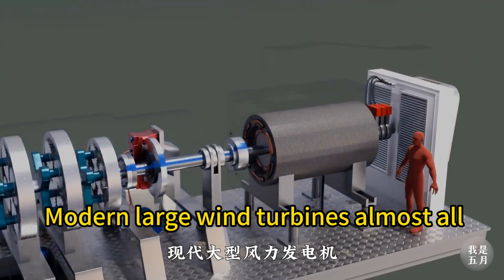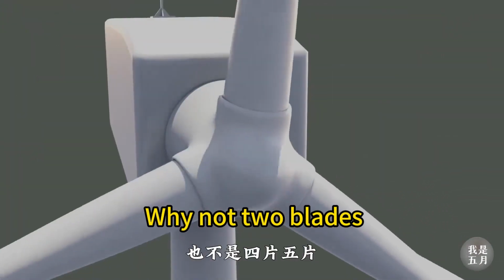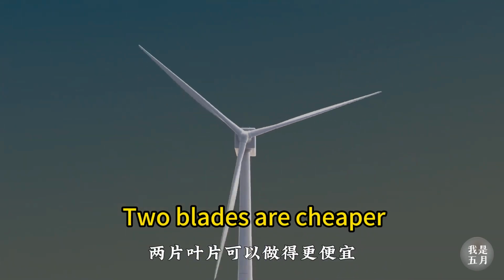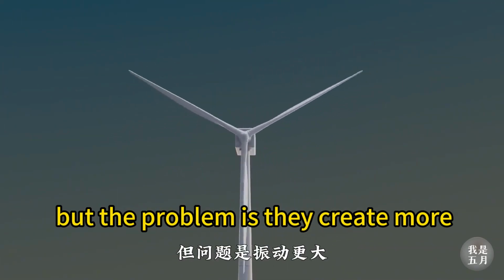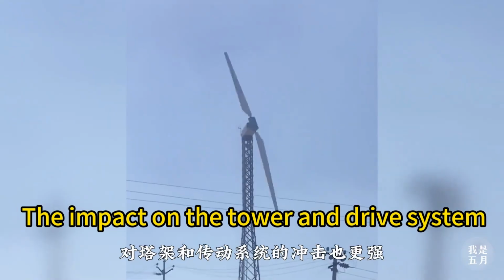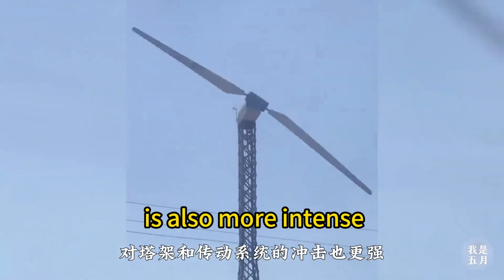Modern large wind turbines almost all use a 3-blade design. Why not 2 blades, or 4 or 5? 2 blades are cheaper and can make money faster. But the problem is they create more vibration and noise. The impact on the tower and drive system is also more intense.